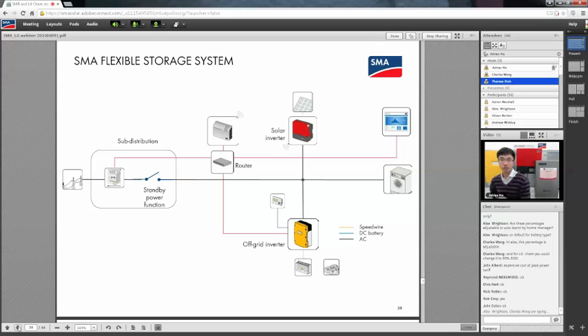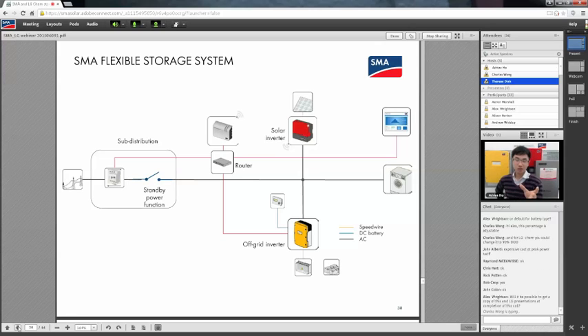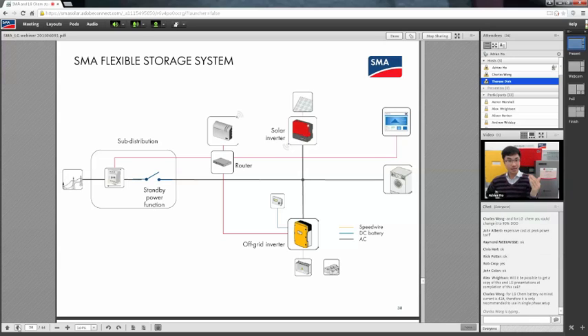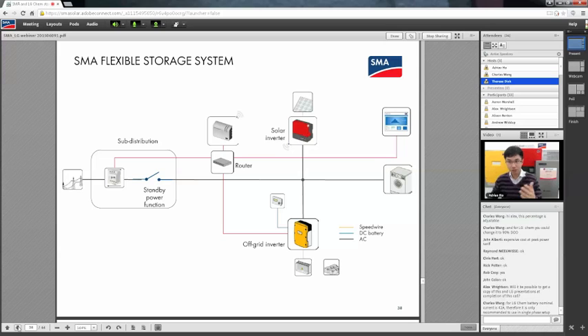For on-grid storage, there are basically two setups: self-consumption and backup. This diagram shown here is for backup. In order to have the backup function, you need to disconnect the Sunny Island system, or your home, from the grid, because the Sunny Island is going to boot up power and feed out to the grid - you just can't allow that to happen. So when there's an electricity blackout, the system will disconnect from the electricity grid. You need that sort of mysterious box over there - going through that now.